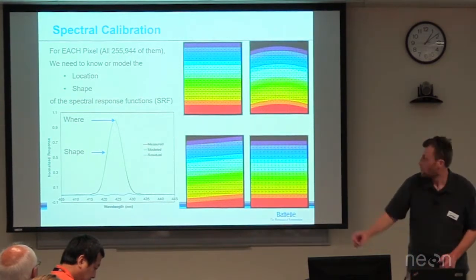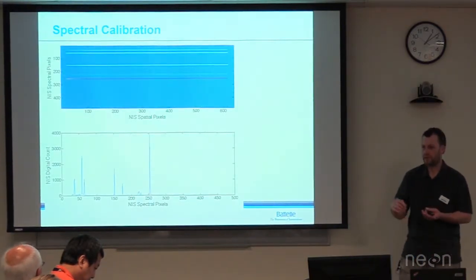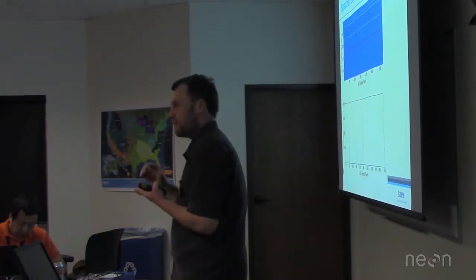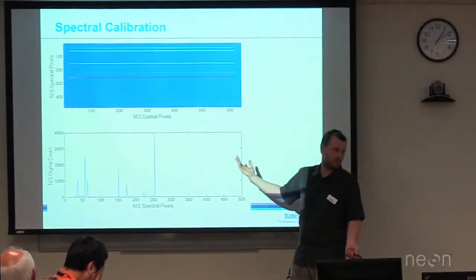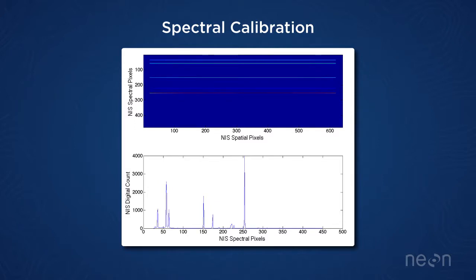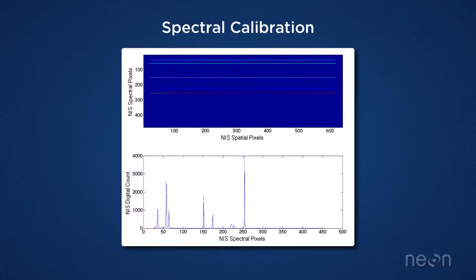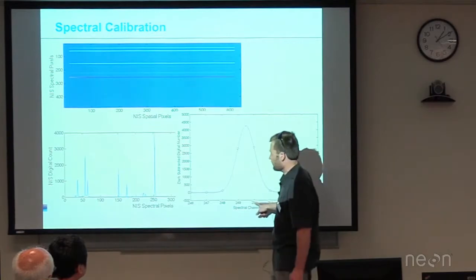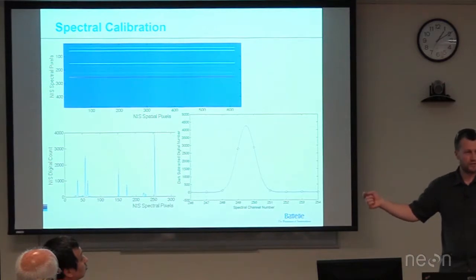One of the ways we determine where the spectral response function is located is to use emission line sources — whether a laser, mercury lamp, or other choices — and put that into the sensor. Since they're emission lines, we know exactly what wavelengths those are, and then we figure out where they fall on our detector. This is an example from a mercury lamp. You can see multiple lines, and a profile through the detector shows distinct peaks. We know where those peaks are and what pixel they fell on. Zooming in on one peak, you can see the tails illuminate other pixels, so we can figure out where the center is. We do this for all spatial pixels for each line.